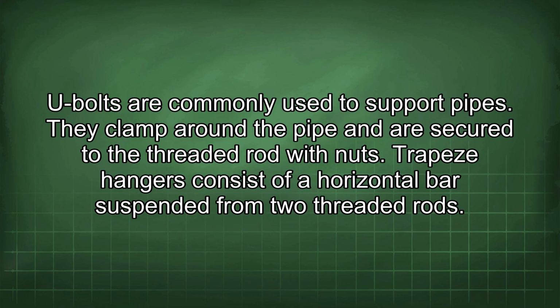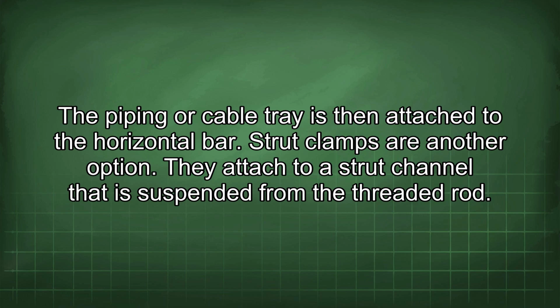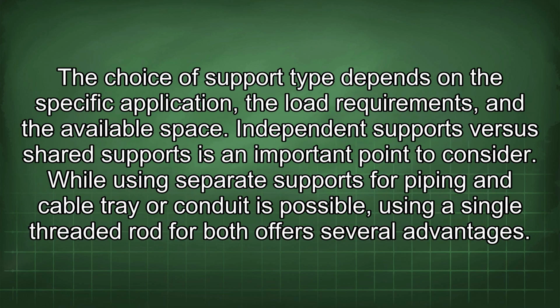U-bolts are commonly used to support pipes. They clamp around the pipe and are secured to the threaded rod with nuts. Trapeze hangers consist of a horizontal bar suspended from two threaded rods. The piping or cable tray is then attached to the horizontal bar. Strut clamps are another option. They attach to a strut channel that is suspended from a threaded rod. The choice of support type depends on the specific application, the load requirements, and the available space.